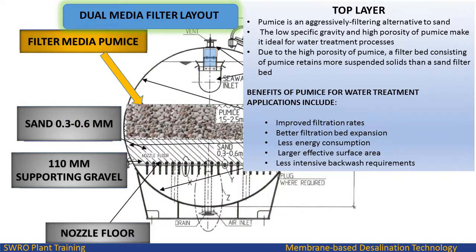Top layer: pumice is an aggressively filtering alternative to sand. The low specific gravity and high porosity of pumice make it ideal for water treatment processes. Due to the high porosity of pumice, a filter bed consisting of pumice retains more suspended solids than a sand filter bed. Benefits of pumice for water treatment include improved filtration rates, better filtration bed expansion, less energy consumption, larger effective surface area, and less intensive backwash requirement.